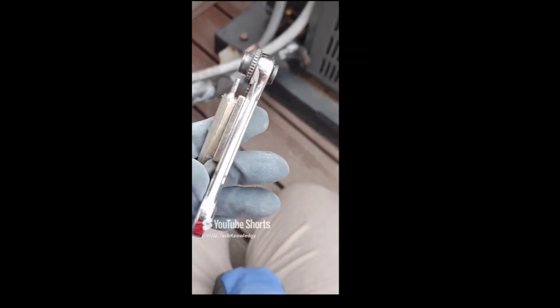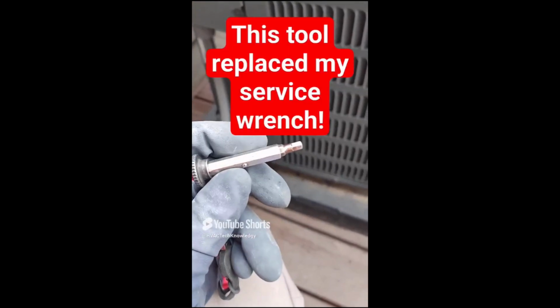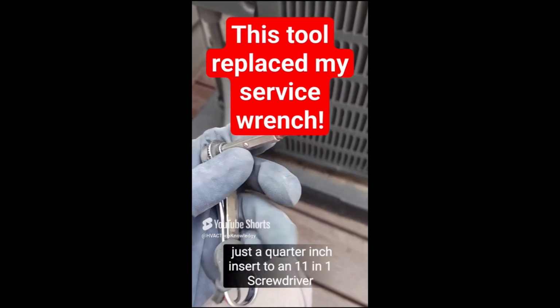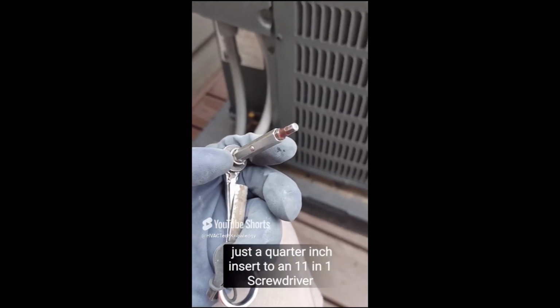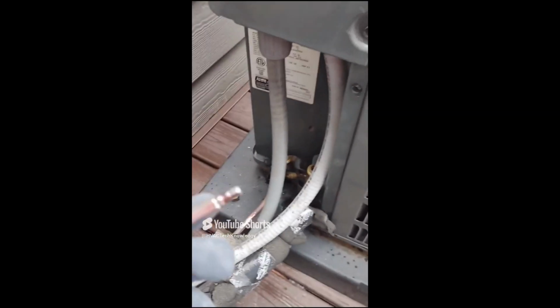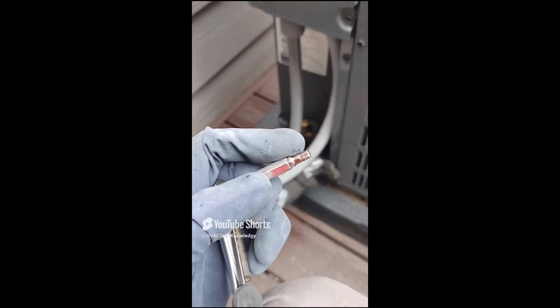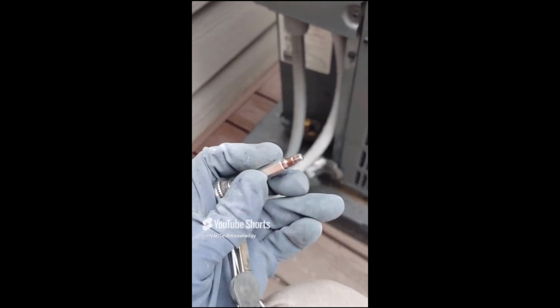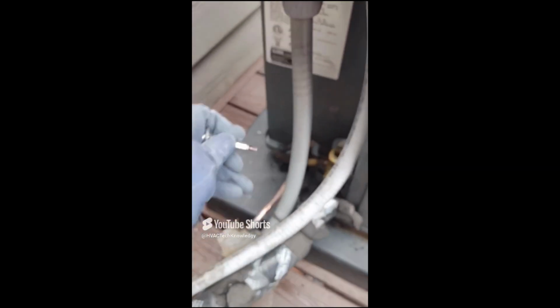Alright, this is a quick short video on how I use this Klein mini ratchet as a tool for pumping down systems. This here is 5/16 outer diameter, so it fits perfectly into the 5/16 drive. And this bit here is a 3/16 drive, which works for gas valves as well as service valves. So we're just going to go ahead and tighten that down.